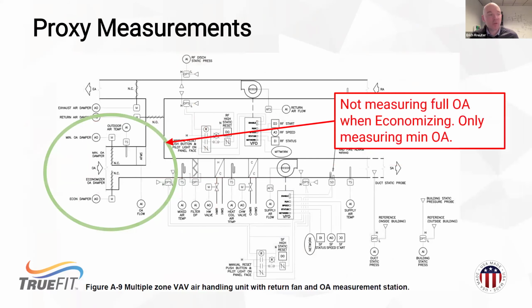The other thing we see typically is on some larger air handlers where you might have a ventilation damper for outdoor air and an economizer damper. The trick here is we're not capturing the full amount of OA typically with a flow station. We're only capturing that ventilation amount, which as soon as we open that economizer damper, now we're not accurately measuring the air changes per hour that could be needed to actually control and ventilate that space.